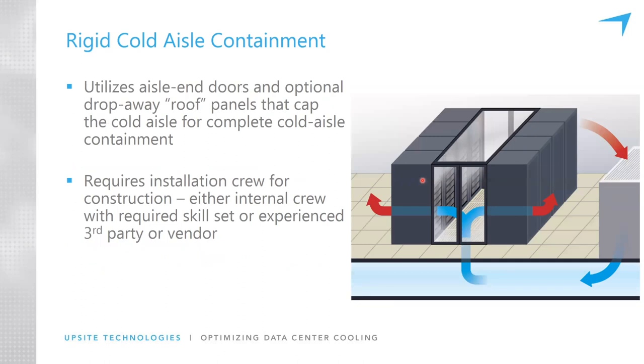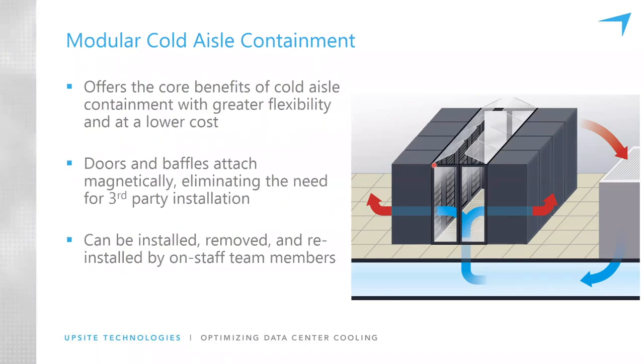Cold aisle containment: of course, we're containing the door, we're containing the end of the aisle on the cold aisle, and putting either a roof on top of the aisle or some sort of baffle to contain that air in the cold aisle. And now the hot air is flowing out and this whole space is hot air, and all that now freely flows back to the cooling units.